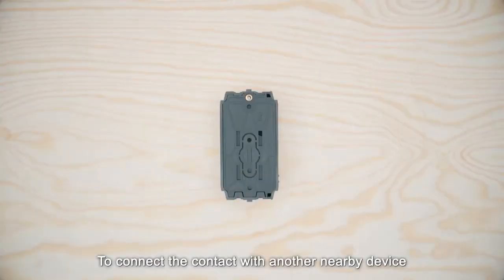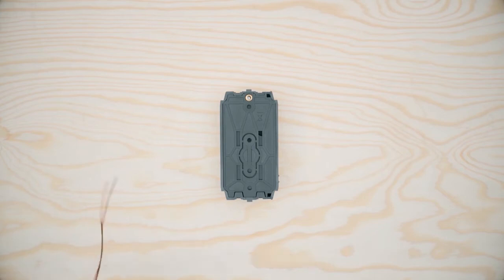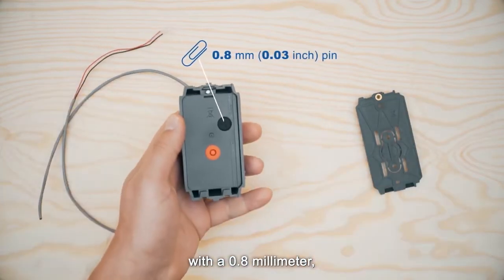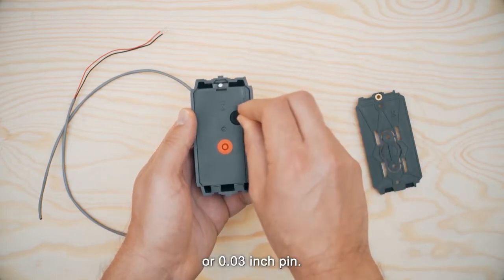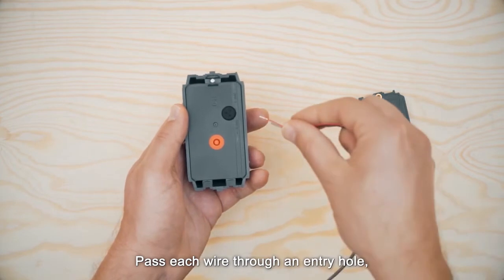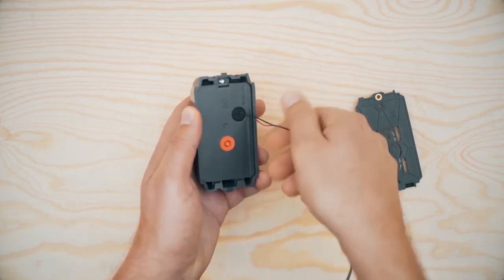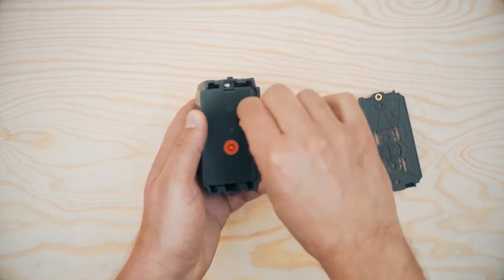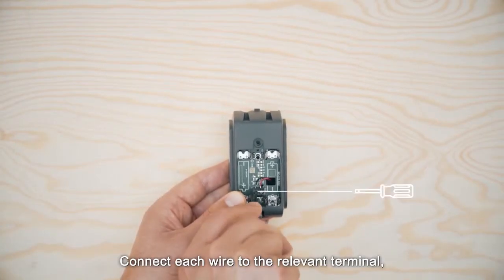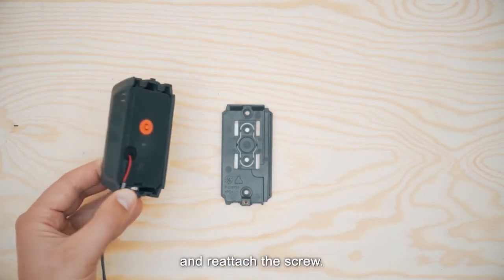To connect the contact with another nearby device via the auxiliary input, start by removing the jacket at the end of the cable to expose the wires. Remove the contacts bracket and perforate the silicone gasket at the back of the device with a 0.8mm or 0.03-inch pin. Pass each wire through an entry hole and out the opposite side. Connect each wire to the relevant terminal and screw the terminal closed using a screwdriver. Put back the contacts bracket and reattach the screw.